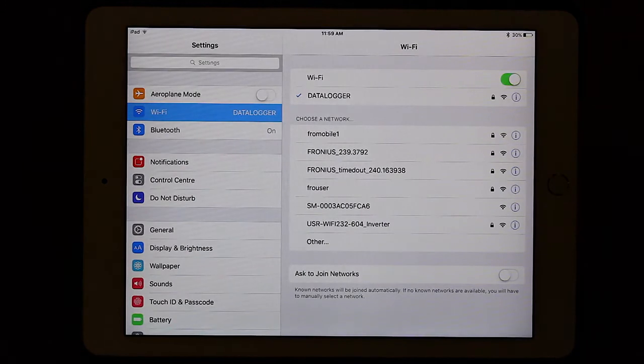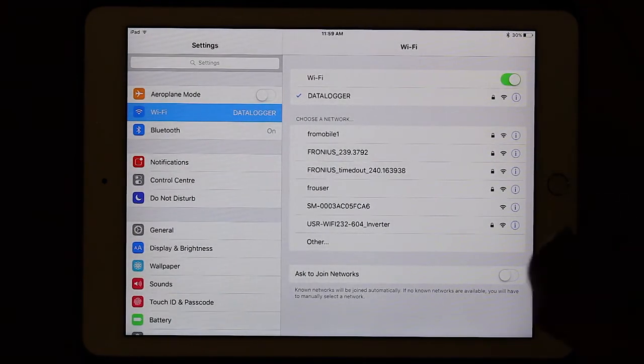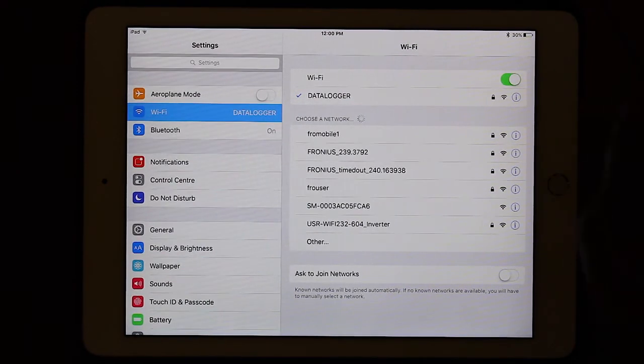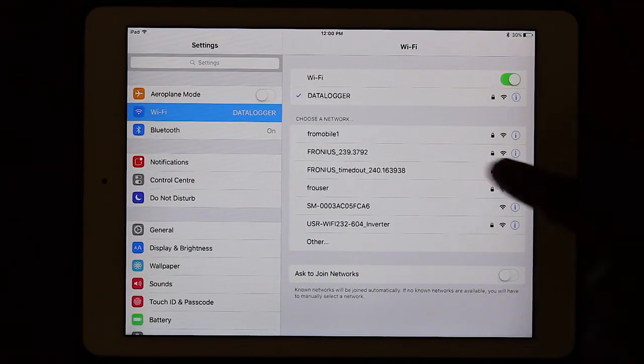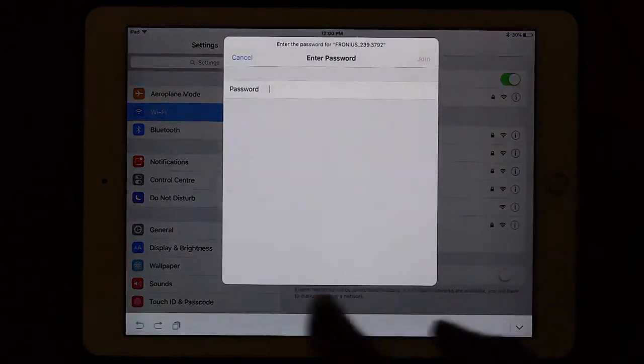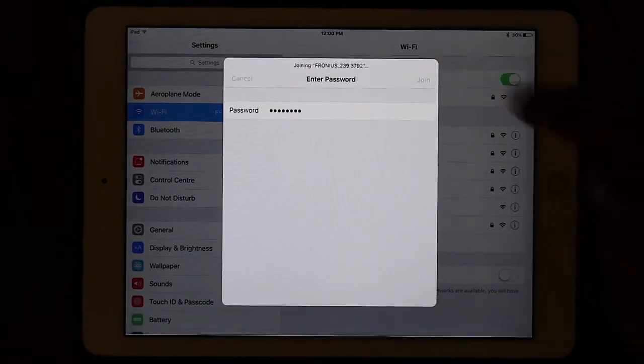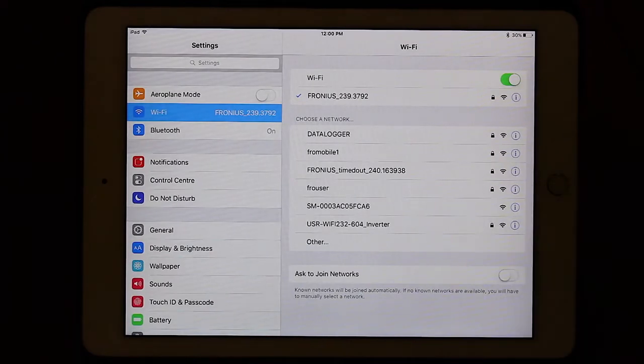Look for the Fronius Wi-Fi access point, which is usually 'Fronius 240' followed by a few digits, or in the case of a Symo Hybrid it's '239' followed by a few digits. Click on it and enter the password, which is '12345678', then click Join. Now we are connected to the Wi-Fi access point of the inverter.